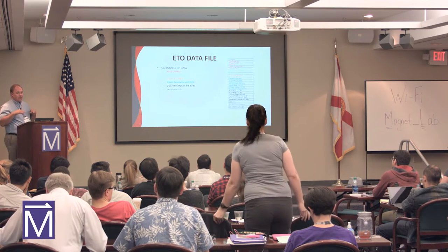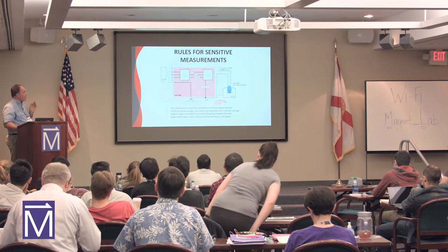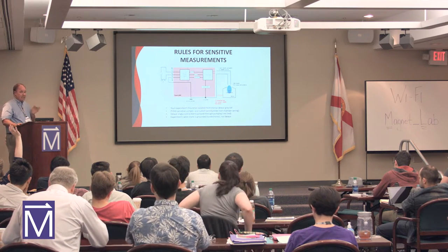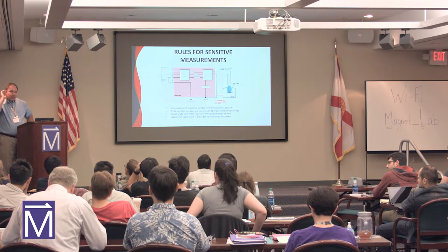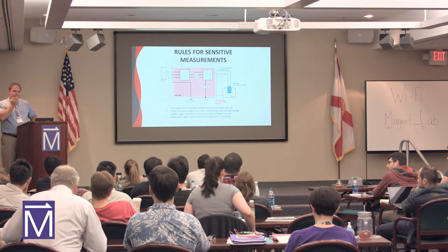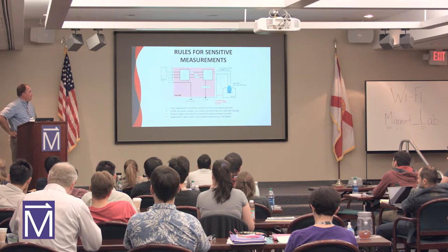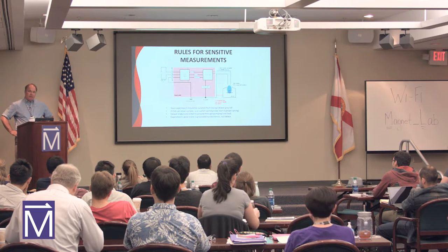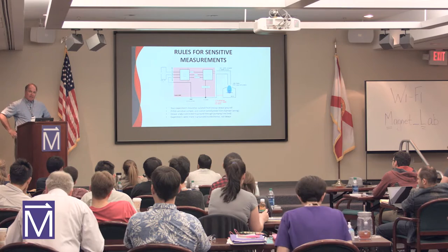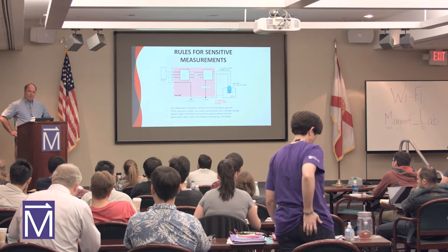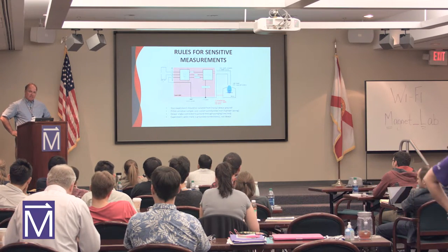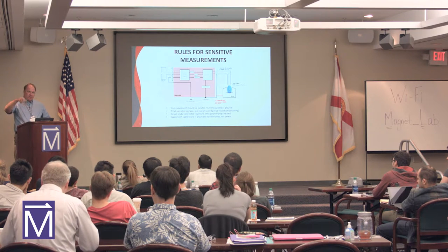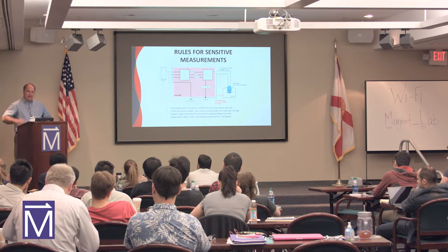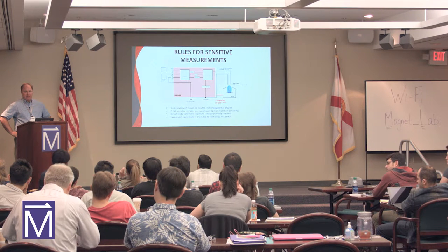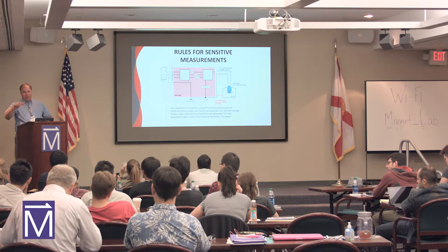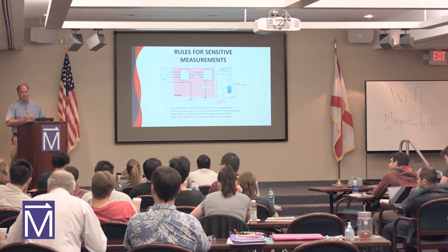So there's a lot of things you can do with the base system, but if you have an ESD sensitive sample, yes? You want to use the base resistivity, and you have to switch around that because of the way the electronics module works on the system. So for the Van der Pauw, you have to make physical connection changes, and the ETO doesn't let you do that easily. Oh, you can't switch the current. Right, there's no multiplexer in the system that does that.